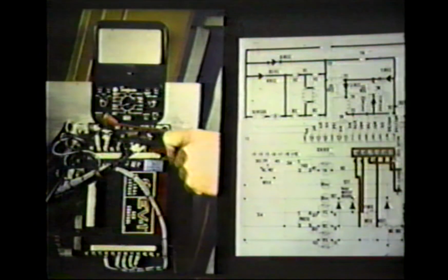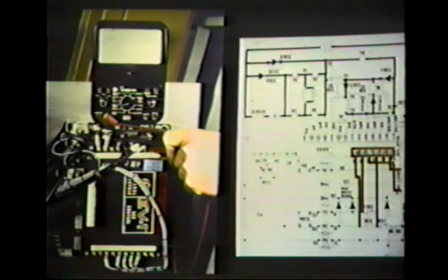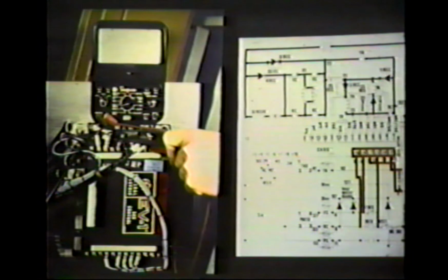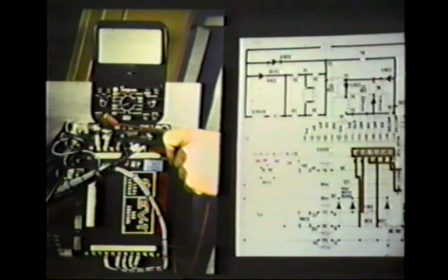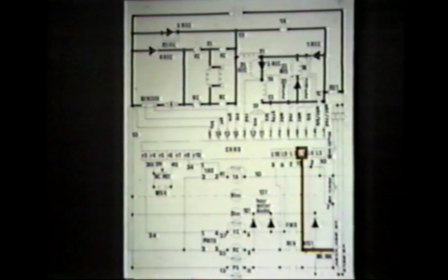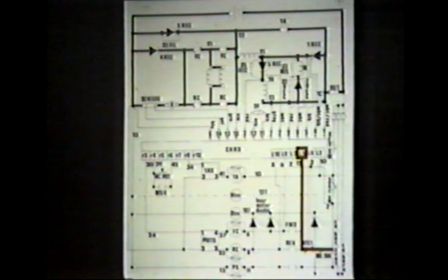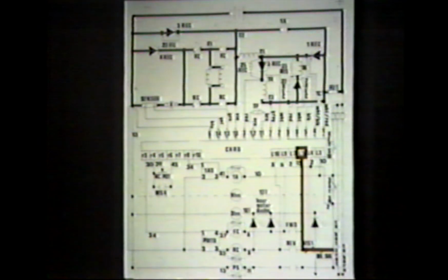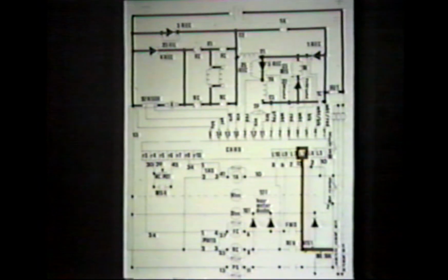Check for positive battery voltage at each of the L terminals 3, 4, 5, 7, 9, and 10 as each switch is activated. If voltage is not present at one of the terminals, check the switch and the wiring that is connected to that particular terminal. All terminals should read 0 volts before its input switch is closed, except for terminal 5, which should read 80% of battery voltage before MS1 is closed. After MS1 is closed, the meter needle should swing up to full battery voltage. If it doesn't, check MS1 and the normally closed brake switch for proper operation.